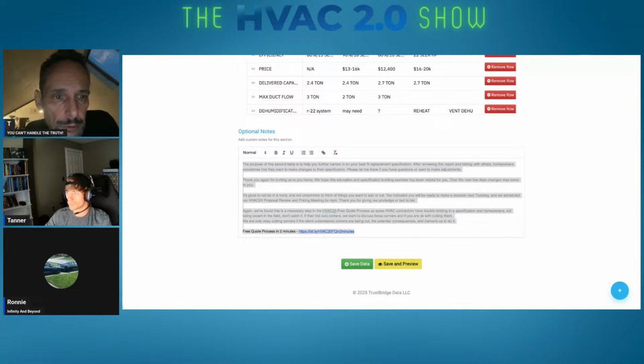And then the duct pressure summary. The pressure inside your ducts is just like blood pressure. It's best to be in a certain range. Too high and there's risk of early failure. Most manufacturers recommend keeping pressure below 0.5 water column, yet 70% of systems in a nationwide database are above that number. 47% are above 0.7, which is commonly agreed upon as the point where decreased equipment life becomes a serious risk. The fixes are typically reducing system size or increasing duct size.